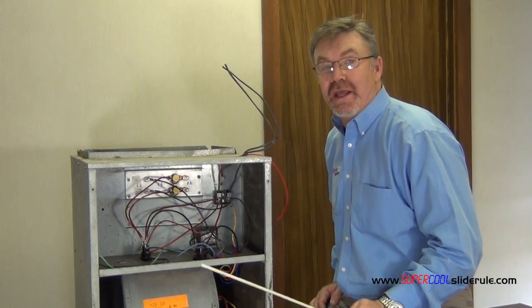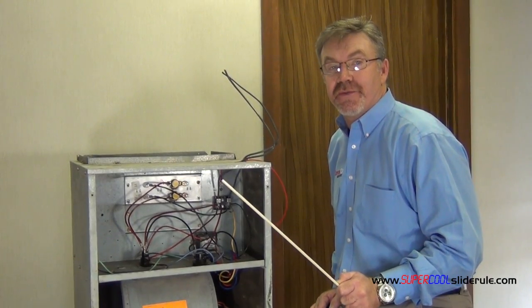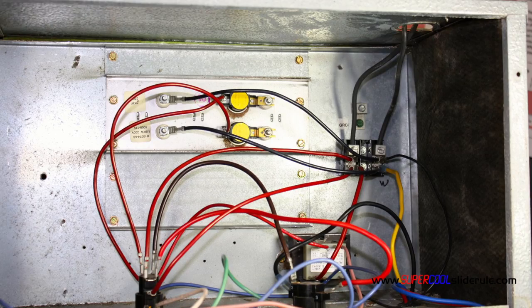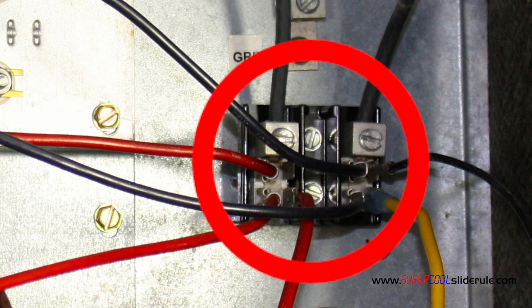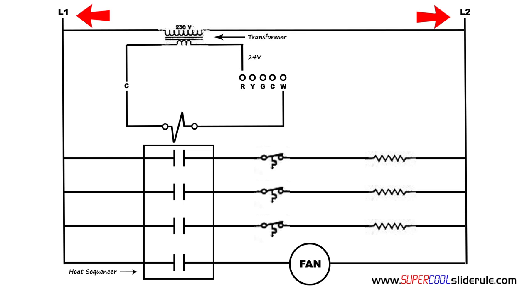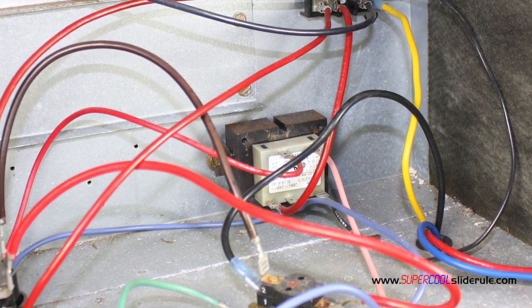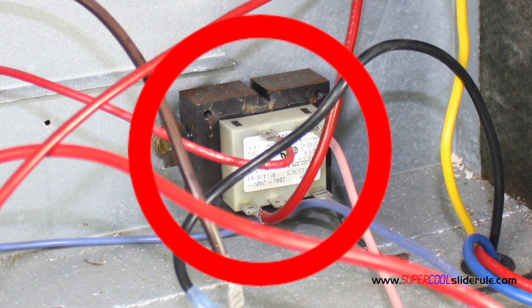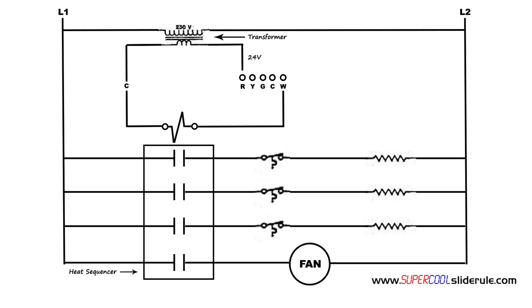Now the way an all electric unit works is as follows. The incoming line voltage is connected at these locations. The electricity flows through the transformer, which converts 240 volts to 24 volts AC. The 24 volts supplies the thermostat with voltage. When the thermostat has a call for heating, it sends the voltage to the W terminal, or the W2 or W3 depending on the particular model of thermostat you have.